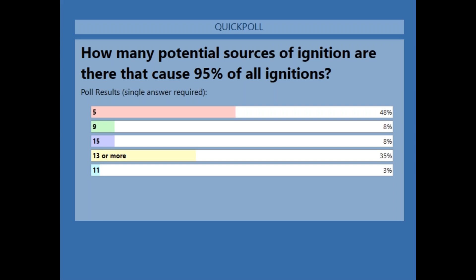Everybody always likes to say this is the flame side of the triangle, or heat. No—it's ignition sources, not just flames or fires: cigarettes, cutting, welding, hot surfaces, heated processes, hot process vessels, or space heating equipment. But also, relevant to the hazardous area industry: mechanical machinery, electrical and instrumentation equipment, friction heating or sparks, impact sparks, sparks from electrical and instrument equipment, stray currents from electrical and instrument equipment, electrostatic discharge sparks, static electricity, lightning strikes, electromagnetic radiation.